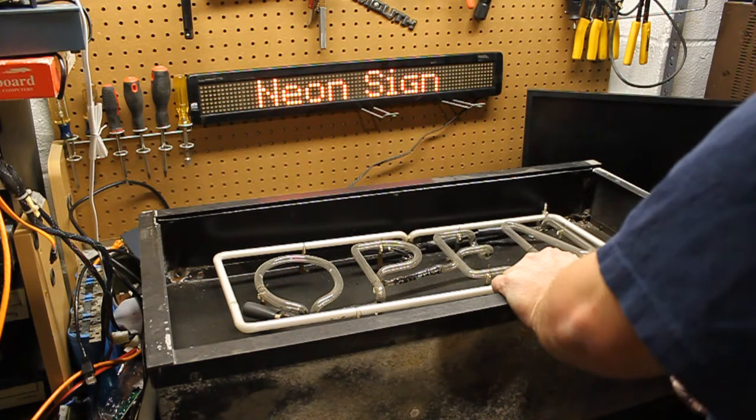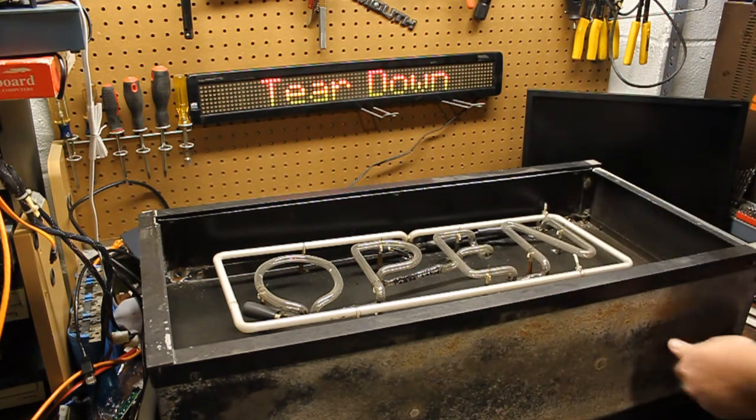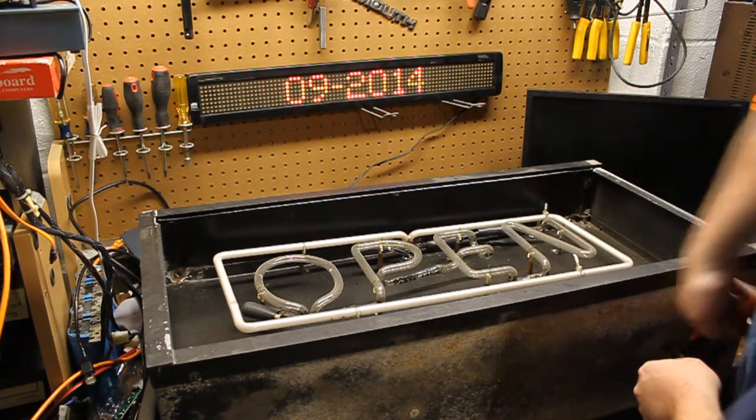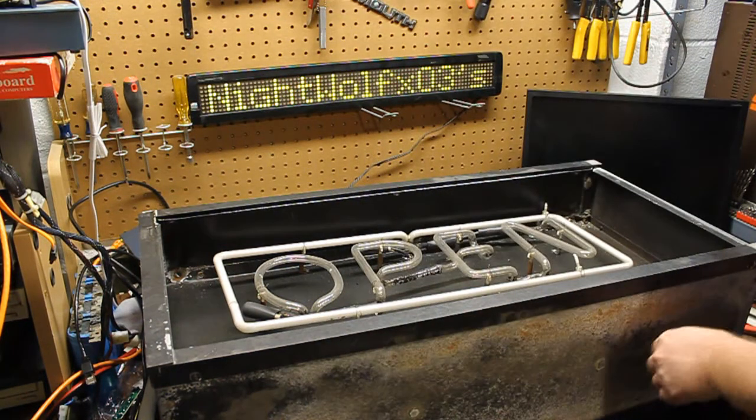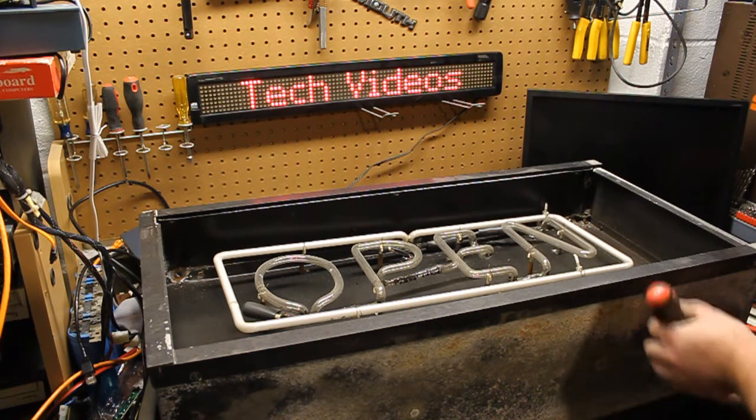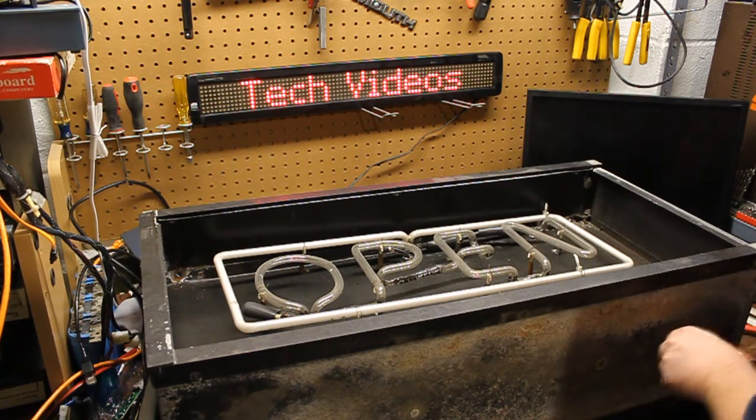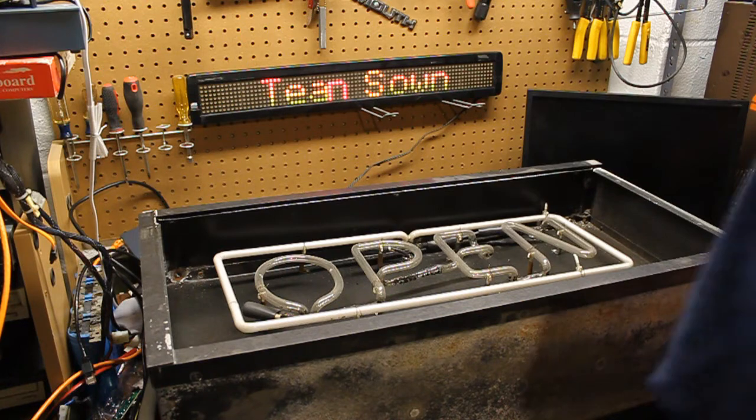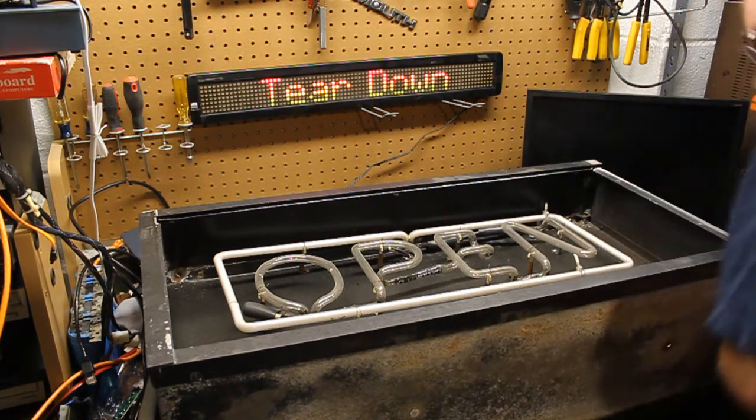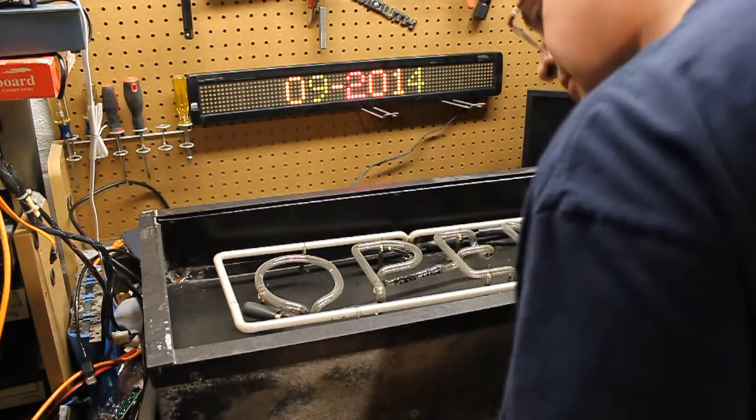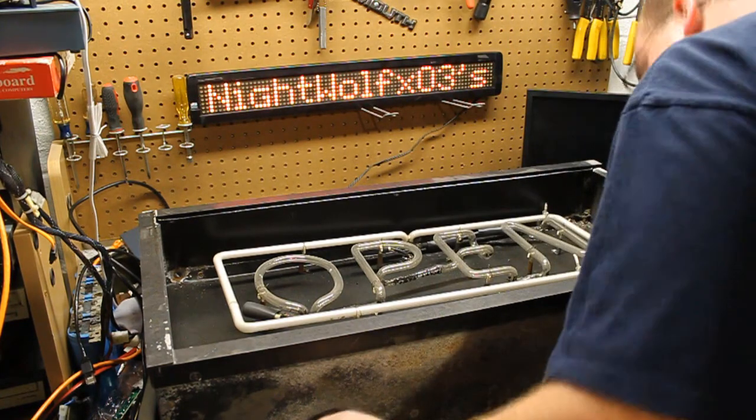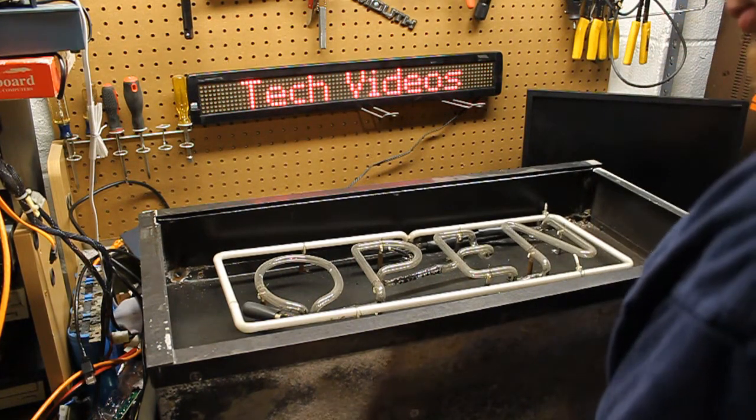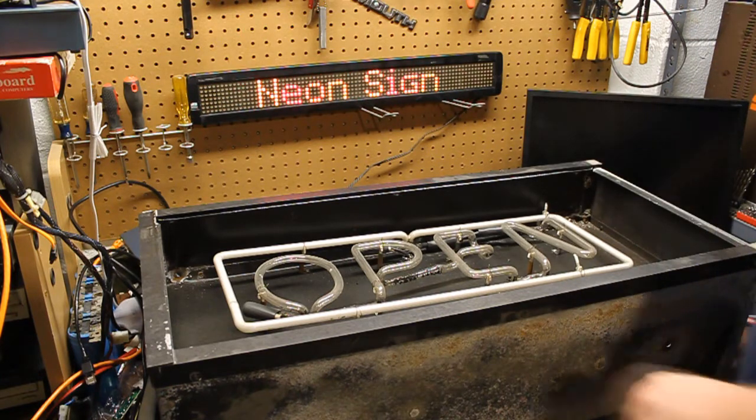We can possibly remove them. I can't believe these are just screwed in here. I'm going to screw you over for that. I don't want to tear up my wires to this. Look at these eye hooks. These might prove useful, but they're pretty rusted. The transformer overall looks fairly healthy. I am slightly concerned with the fact that there is no ground hook to the ground stud on the transformer. We'll see if we can't flip this casing up. I'll show you that here in a minute.